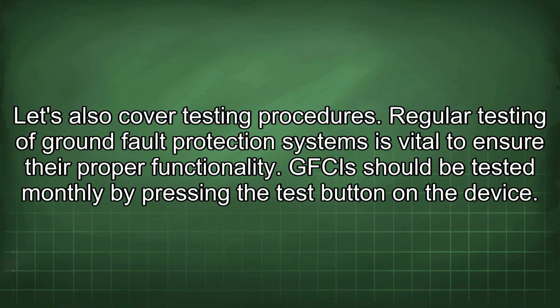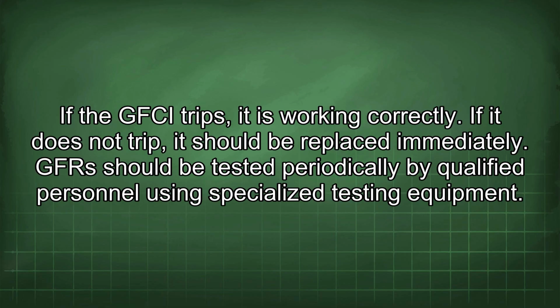Let's also cover testing procedures. Regular testing of ground fault protection systems is vital to ensure their proper functionality. GFCIs should be tested monthly by pressing the test button on the device. If the GFCI trips, it is working correctly. If it does not trip, it should be replaced immediately.